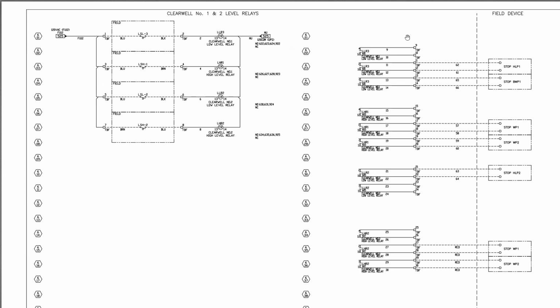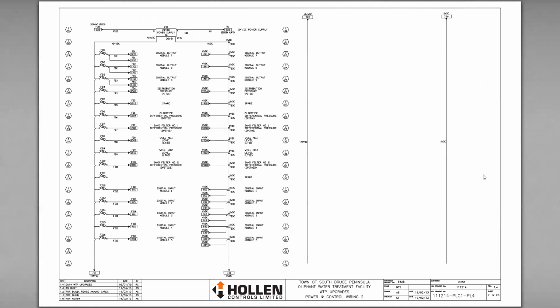This particular site was completely hardwired before we added this PLC in. So there were more floats that, when the level got too low, actually started pumps instead of just interlocking them, and we added a PLC to it to give them some automation. So when you have to do such a big upgrade with existing equipment and existing infrastructure, unfortunately, you don't always have the luxury of being able to make up wire numbers for that equipment.